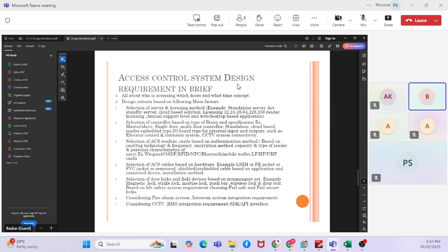The selection of controls also involves master-slave concepts versus IP-based systems. When checking specifications, sometimes it asks for master-slave concept, and sometimes they look for only IP-based solutions, so we have to choose based on the specifications. In master-slave, the master is an IP-based controller and the slaves are RS485, a bus technology chained in a loop from master to multiple slaves. When we go with IP-based, all the controllers should be IP-based.